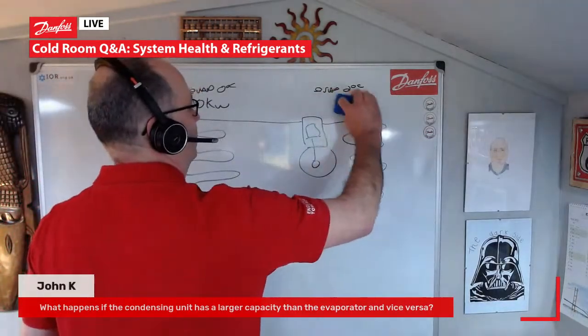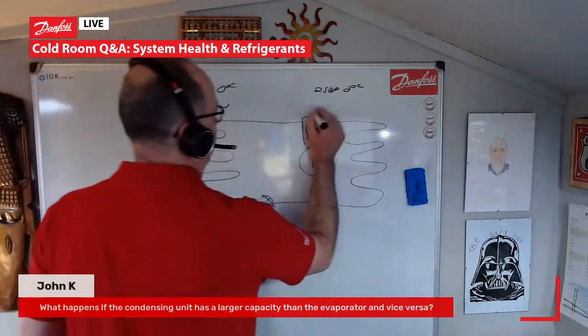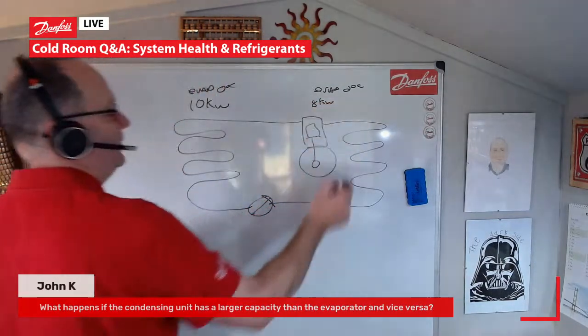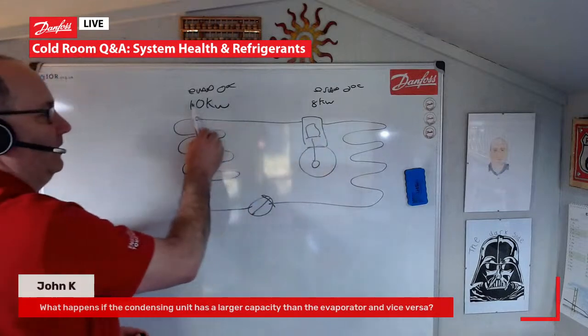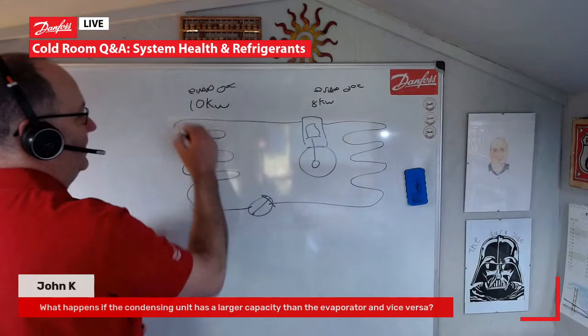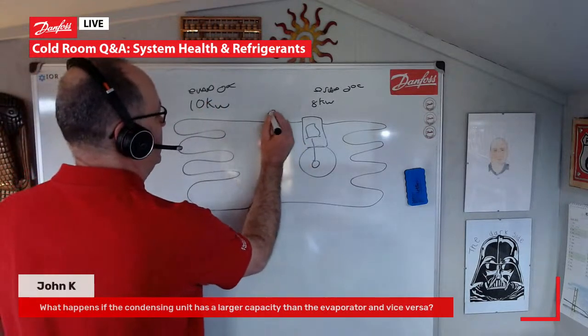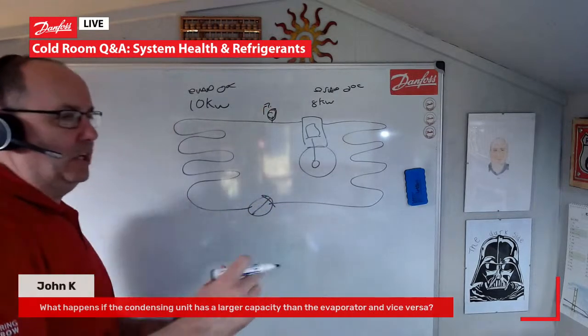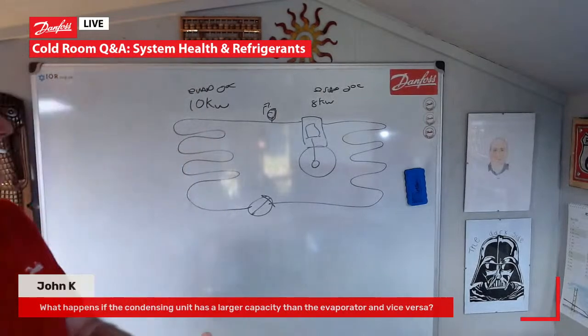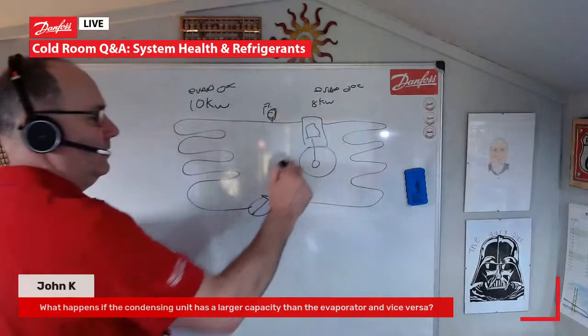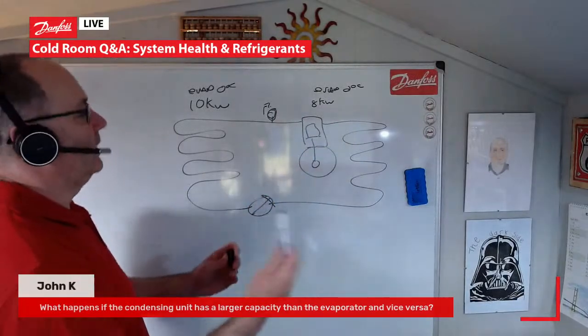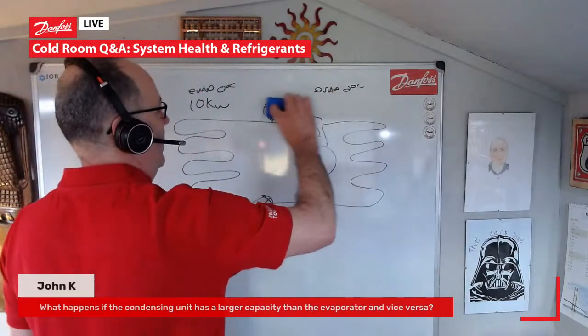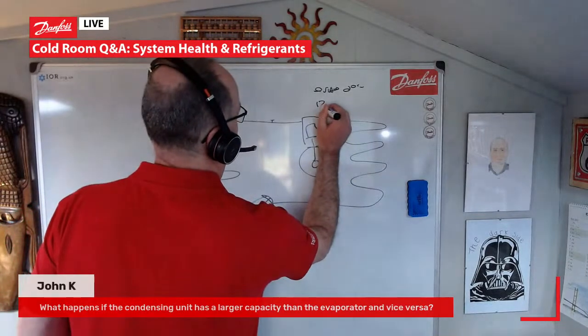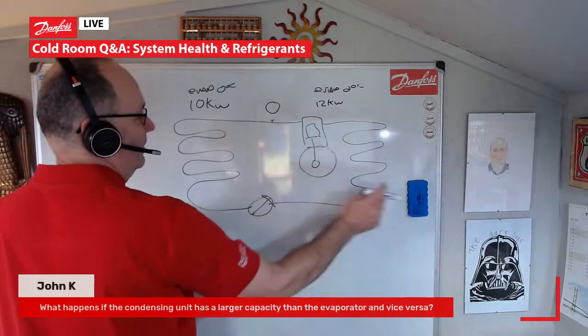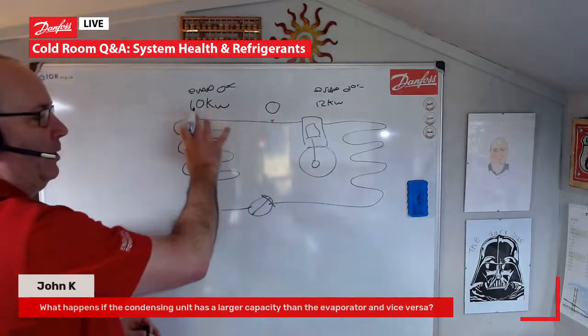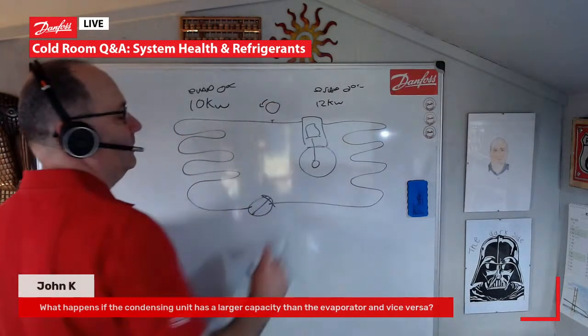If, however, we keep a 10 kilowatt evaporator and we have an 8 kilowatt compressor, that compressor is smaller in capacity than the evaporator. What will happen is that because the evaporator is larger, our suction pressure coming back to our machine will rise. It might not rise by much, maybe a few PSI, which in effect is good because it's giving our compressor something to work at. If we then change things around and say we've got a 12 kilowatt compressor, that can now do more duty than our evaporator can actually provide, so our suction pressure is going to fall a little bit.